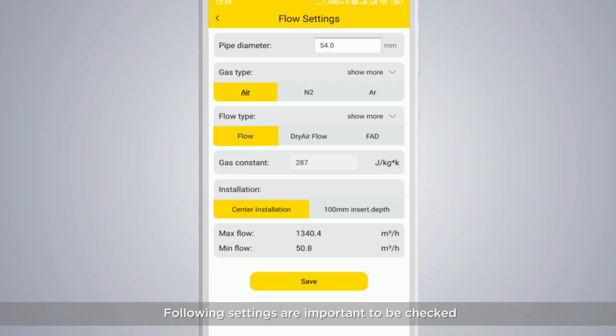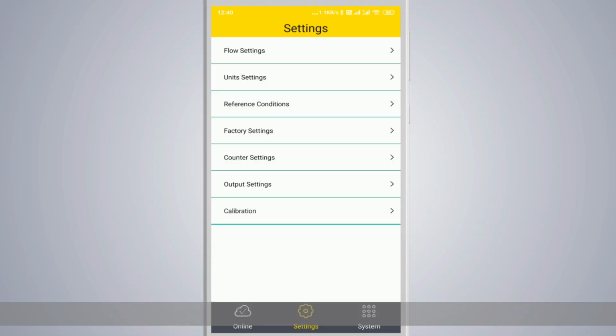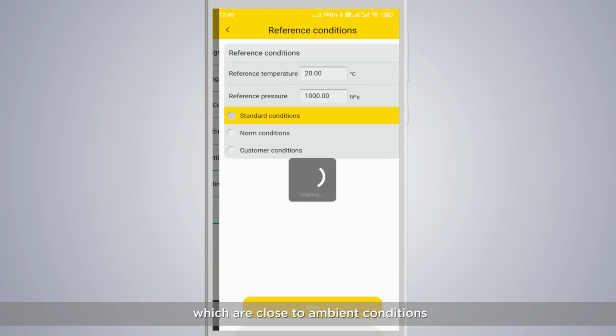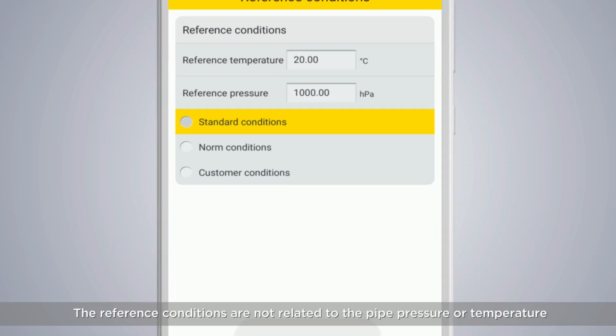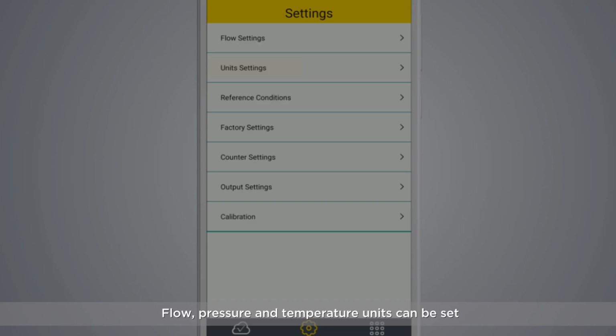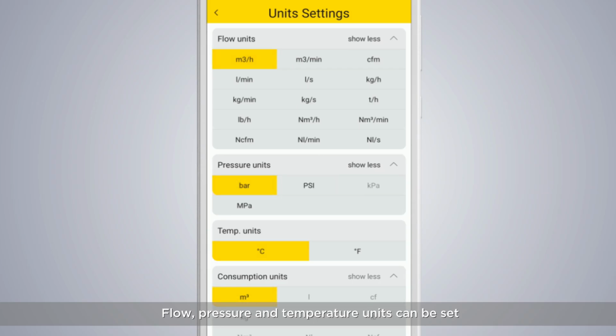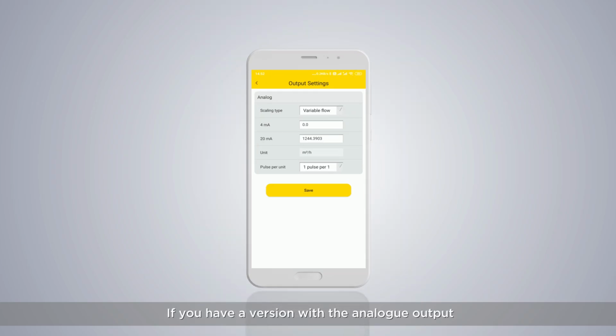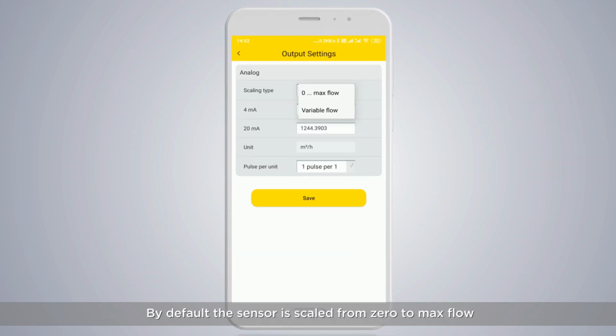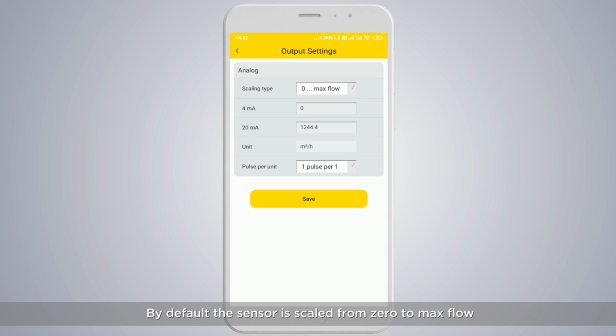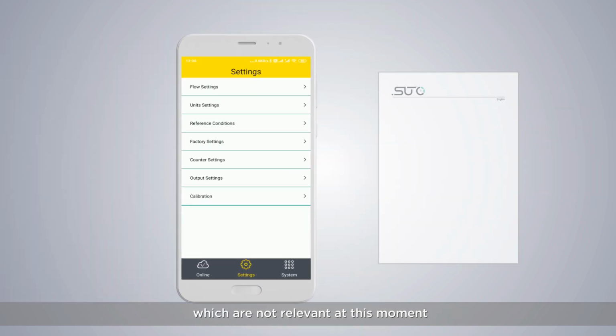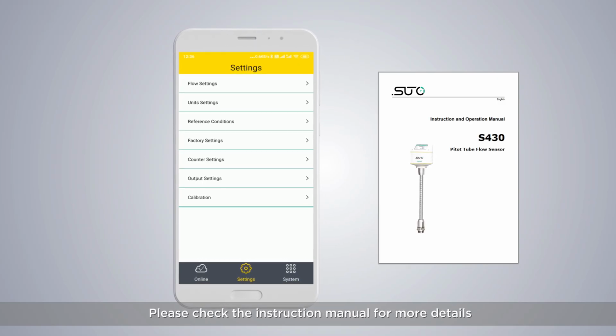The following settings are important to be checked and, if required, modified. Gas flows are always calculated to standard or norm conditions, which are close to ambient conditions. The reference conditions are not related to the pipe pressure or the temperature. Do not enter your pipe pressure or temperature under reference settings. This will lead to wrong measurements. Flow, pressure, and temperature units can be set. If you have a version with the analog output, you can enter the scaling for the analog output. By default, the sensor is scaled from 0 to max flow. There are a couple of more settings which are not relevant at this moment. Please check the instruction manual for more details.